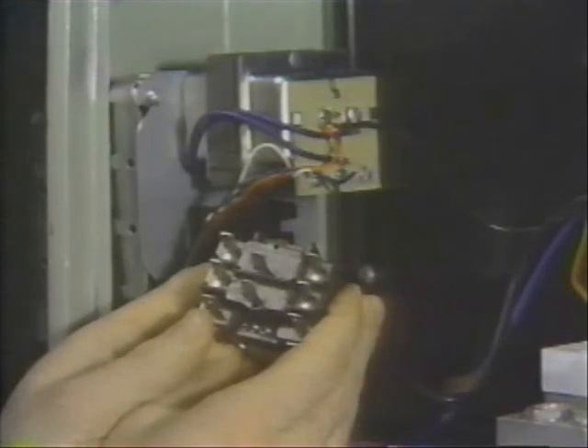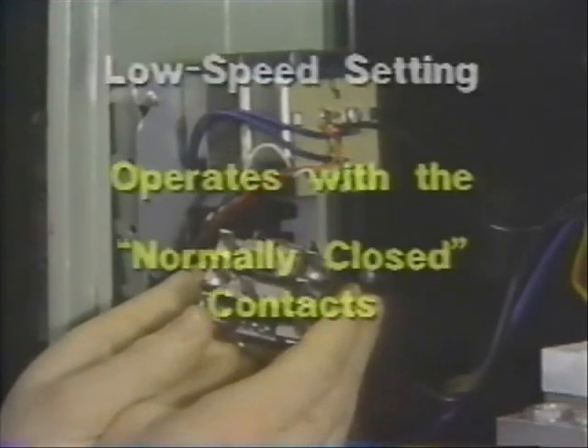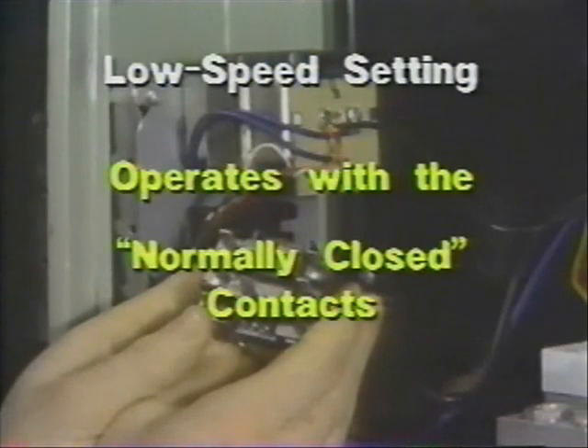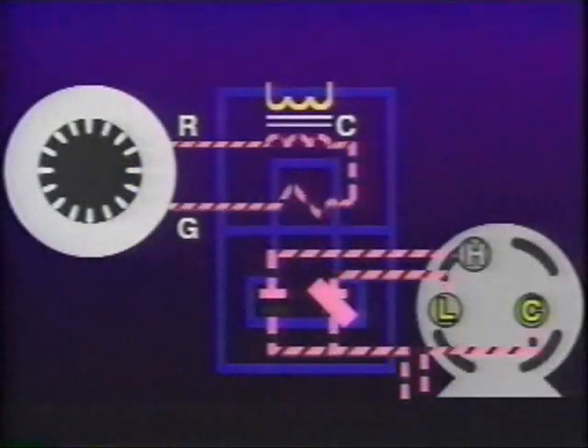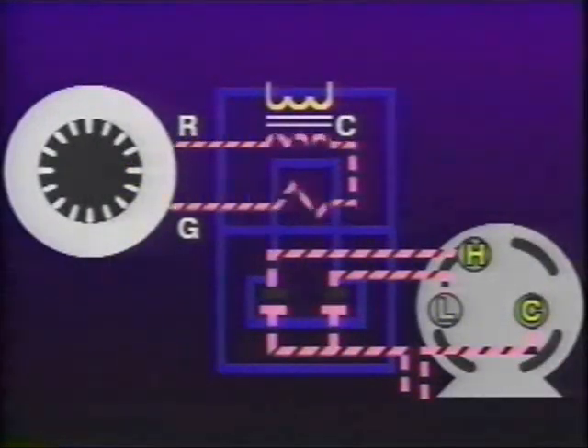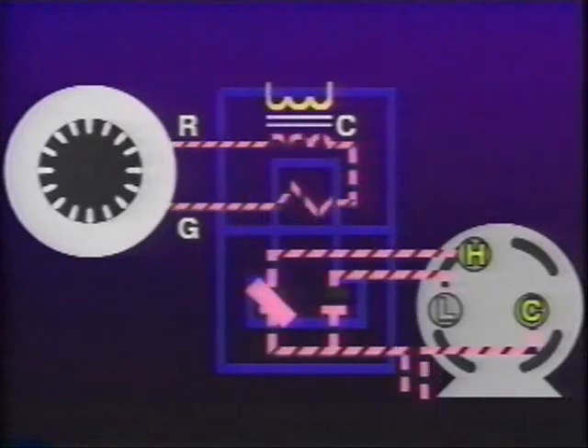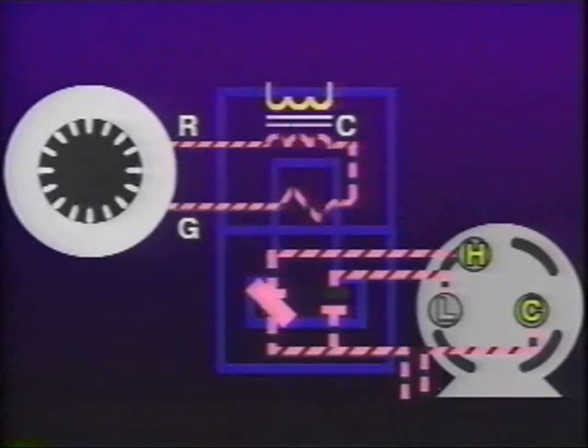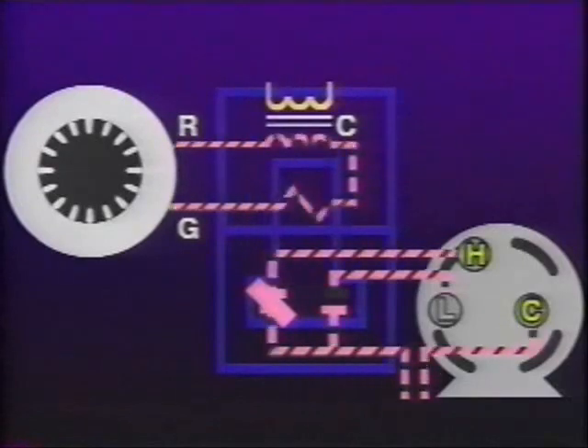Many combination systems have two-speed fans, low speed for heating, high speed for cooling. This requires a single-pole double-throw relay, as shown in this fan center hookup. The low speed for heating operates through normally closed contacts in the relay. On a call for cooling, the normally closed contacts open, cutting off power to the low-speed fan. The normally open contacts then close to energize the high-speed windings of the fan motor.